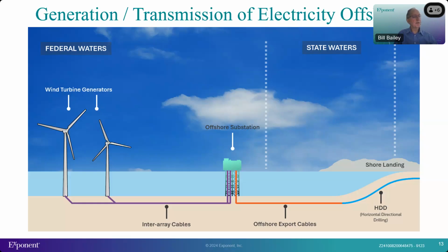Typically, the connection between the offshore export cables and onshore underground cables is made by passing the cables through conduit tubes deep underneath the ground, using a technique called horizontal directional drilling, or HDD. The virtue of HDD is that the cables are protected from damage and avoid any disturbance to the shore above.